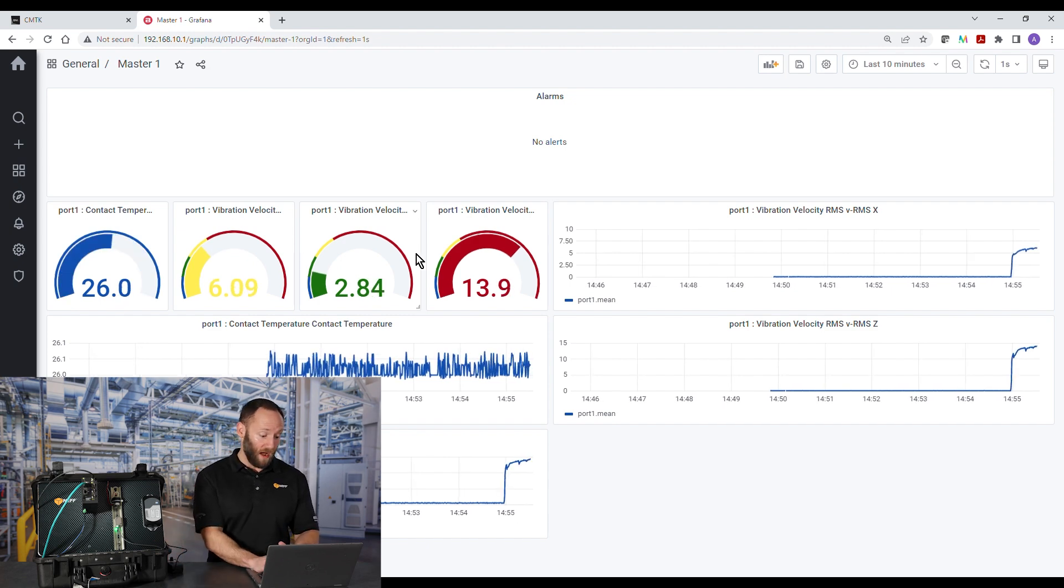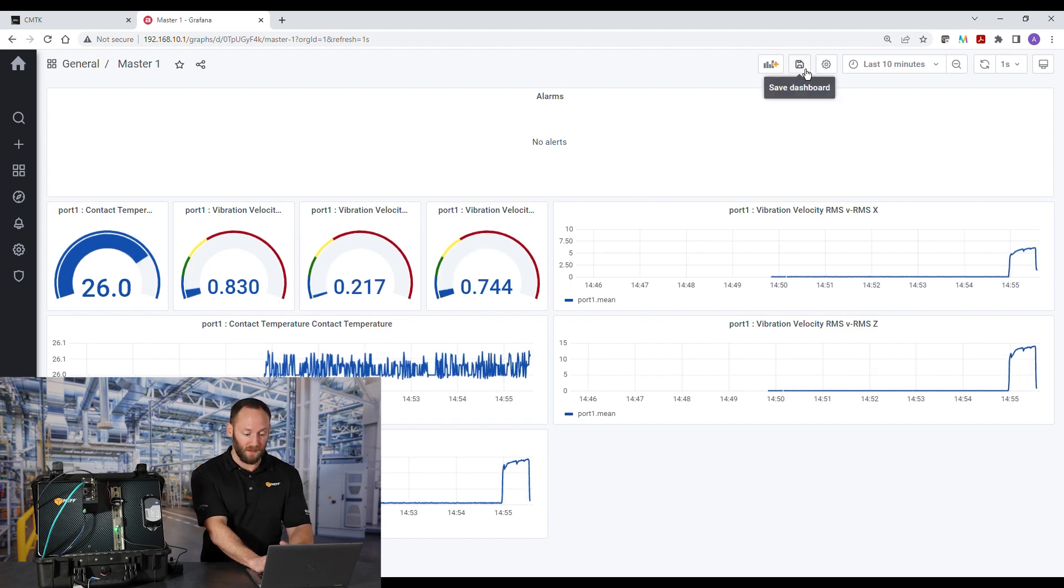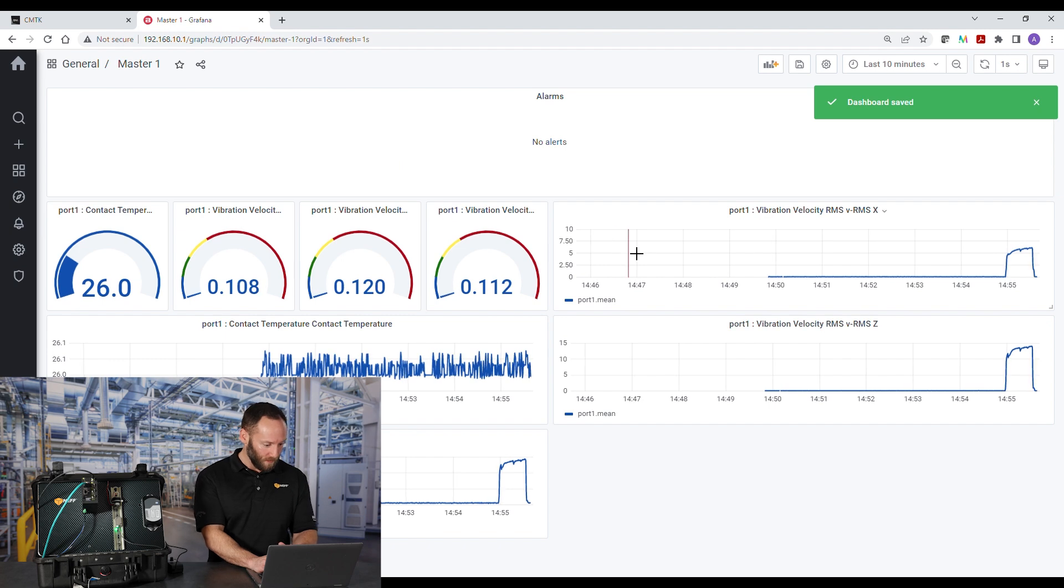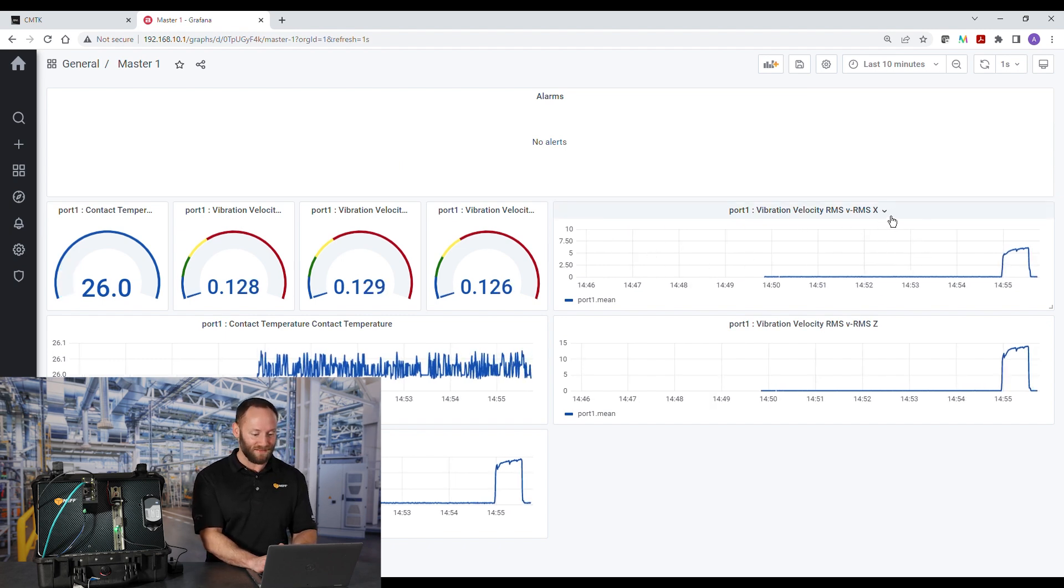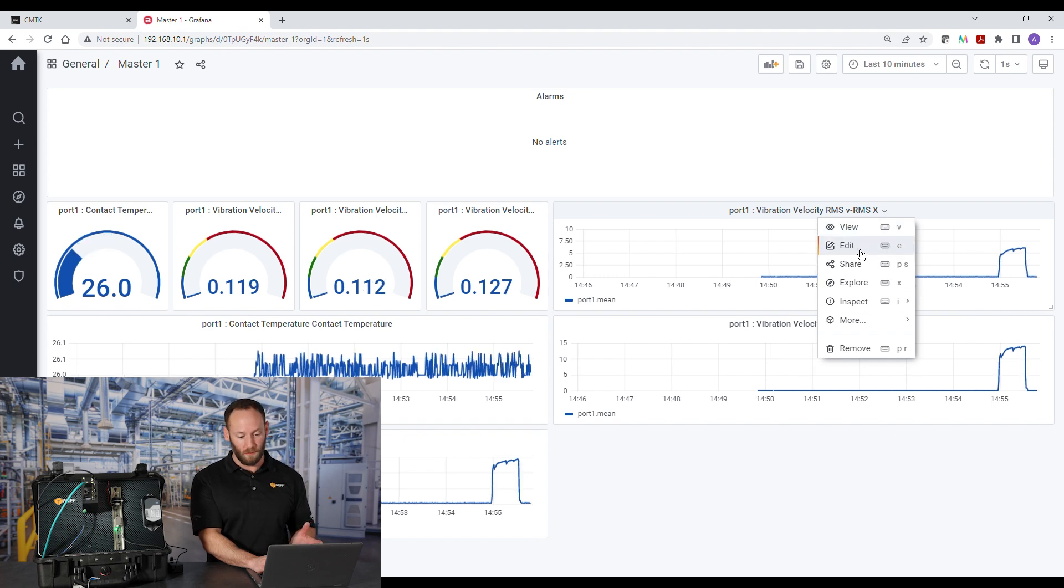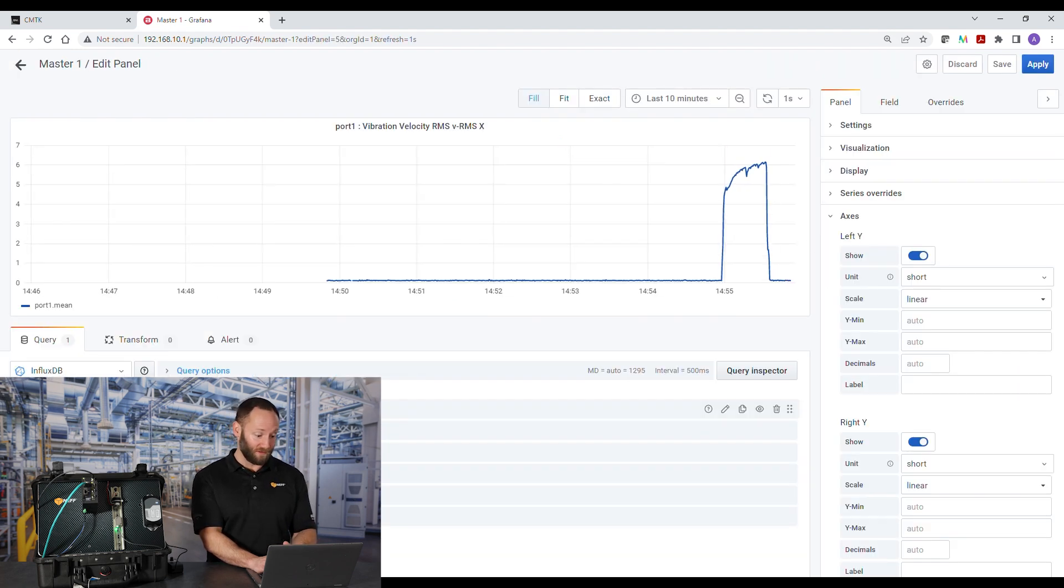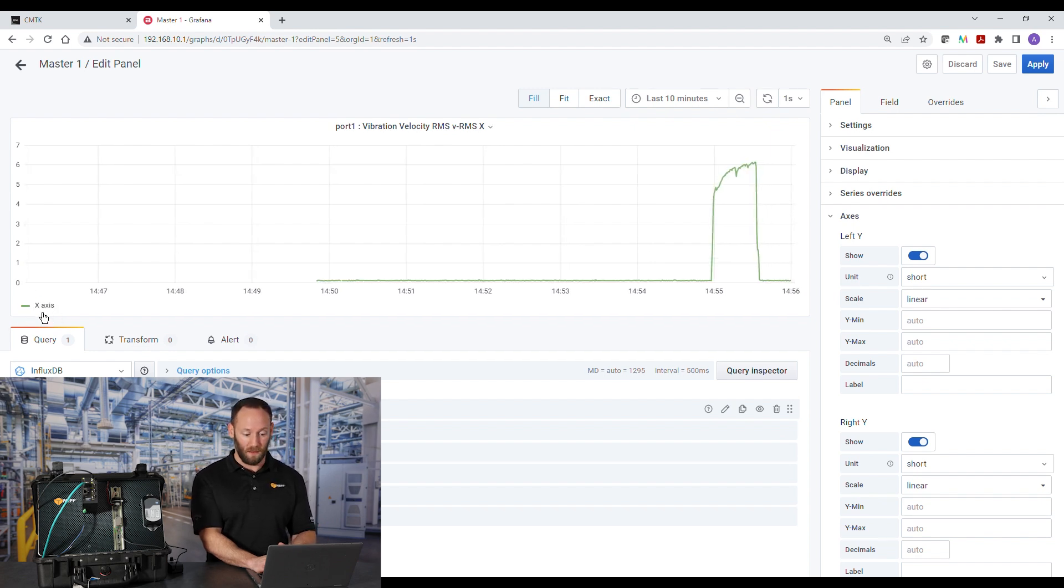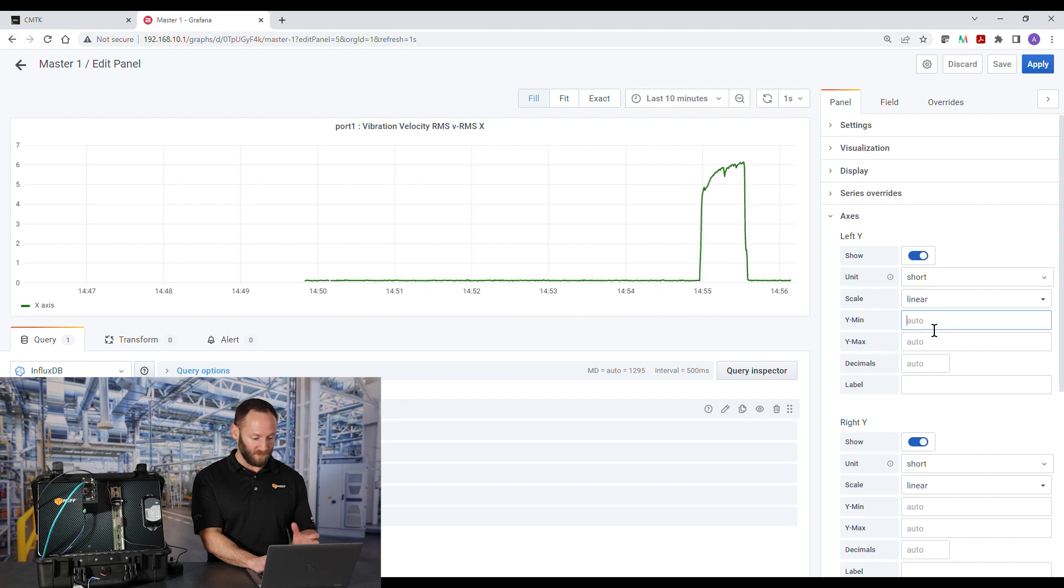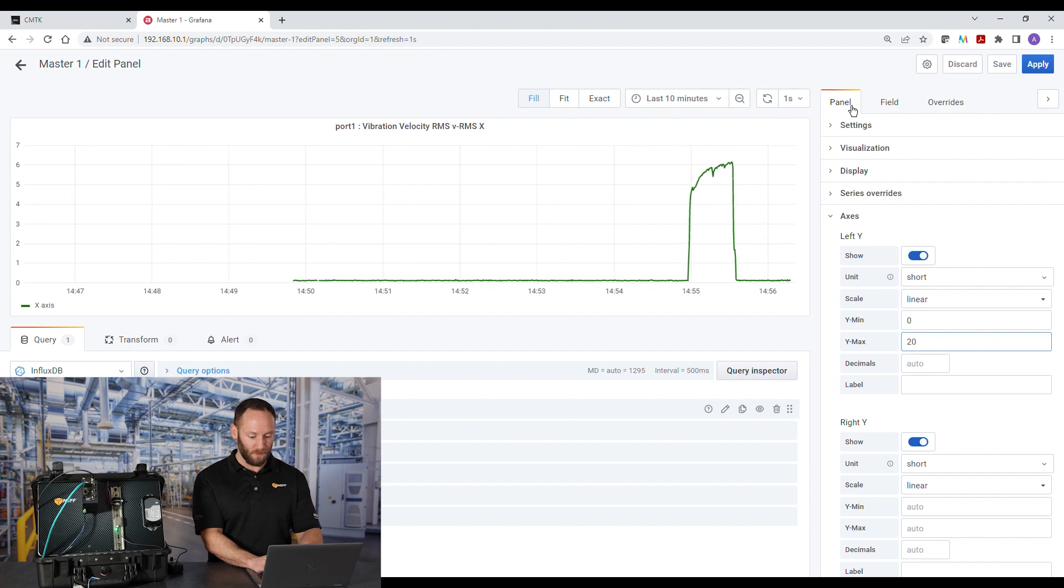Next, let's look at the graphs, but we'll save first. Save early, save often. That's what my high school teacher said. Next, we'll look at the vibration velocity on the X axis. So again, we'll click the arrow for the drop down menu and edit. The first thing I like to do is alias the graph. So I'll just say X axis. And now we can choose different colors. I'm going to leave it green. Next, I want to change scaling. I don't want it to auto scale. So I'll fix it to 0 to 20 millimeters per second in the X axis under panel.